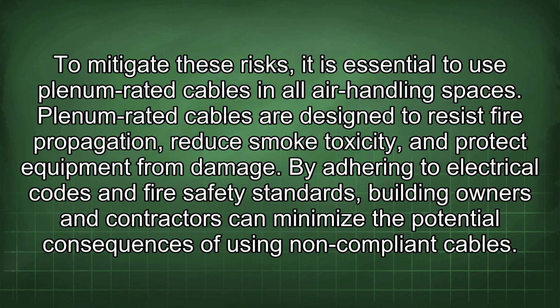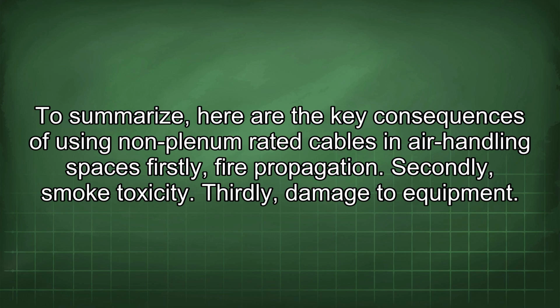To mitigate these risks, it is essential to use plenum-rated cables in all air handling spaces. Plenum-rated cables are designed to resist fire propagation, reduce smoke toxicity, and protect equipment from damage. By adhering to electrical codes and fire safety standards, building owners and contractors can minimize the potential consequences of using non-compliant cables. To summarize, here are the key consequences of using non-plenum rated cables in air handling spaces.